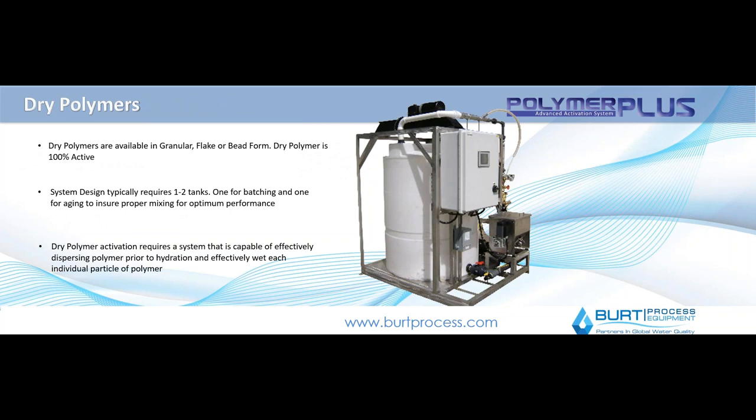In addition to liquid polymer systems, Burt Process Equipment also makes dry polymer-based systems. The pros and cons of using liquid versus dry polymer is kind of an owner or user preference. Dry polymer is easier to buy in bulk if you need a lot of it, as opposed to buying gallons of liquid polymer. But the actual apparatus is a little bit different — you have to get the polymer from solid into solution for makeup, and then go through more of a chemical injection system like a ChemPlus. You don't have the same concerns for polymer activation when utilizing dry polymer.